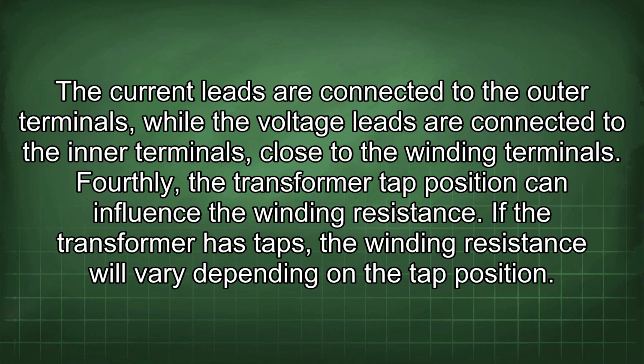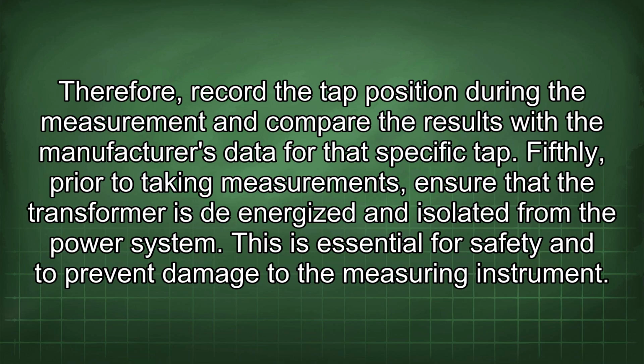Fourthly, the transformer tap position can influence the winding resistance. If the transformer has taps, the winding resistance will vary depending on the tap position. Therefore, record the tap position during the measurement and compare the results with the manufacturer's data for the specific tap.